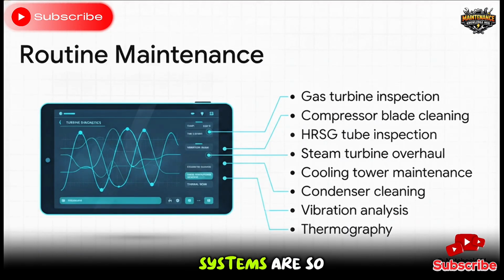And because these systems are so incredibly complex, keeping this dual-cycle plant running smoothly requires some seriously rigorous routine maintenance. Operators can't just flip a switch and walk away. Maintenance ranges from deep cleaning the compressor blades and inspecting the combustion chamber to high-tech diagnostics like vibration analysis and thermography. They also have to constantly monitor the HRSG tubes, clean the condenser, and maintain those cooling towers.